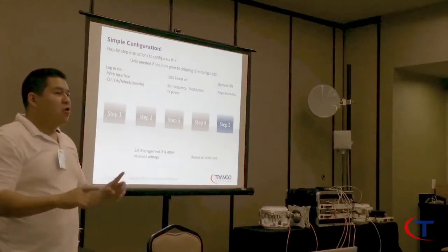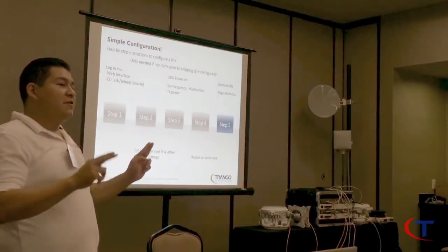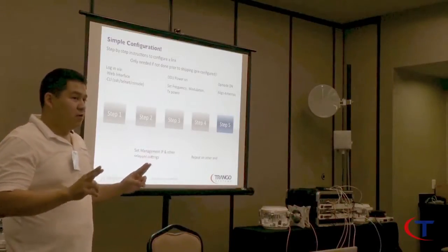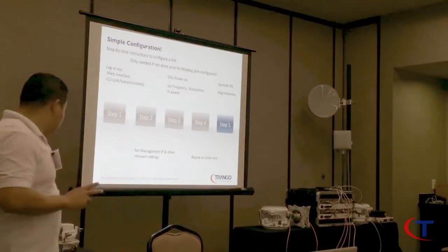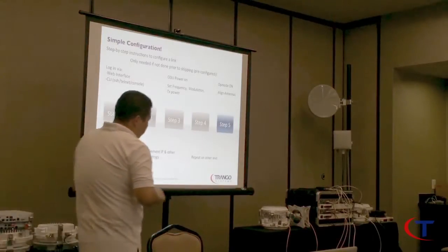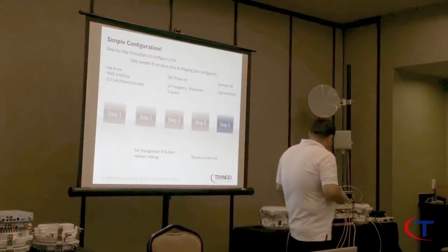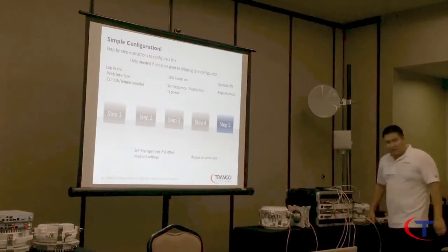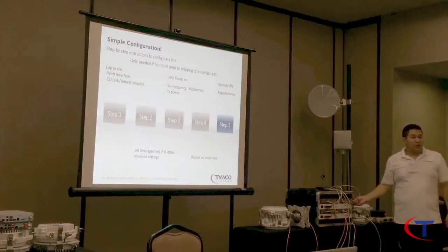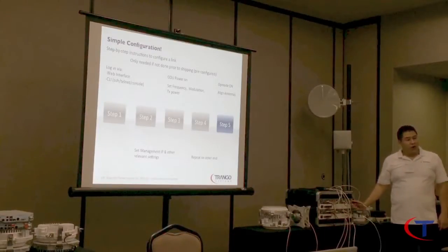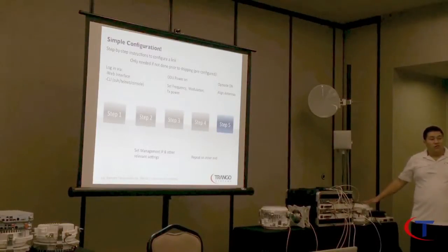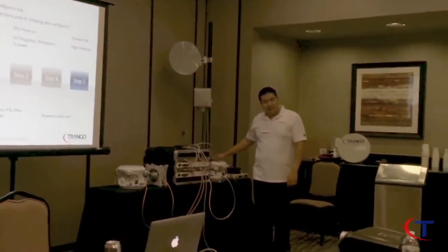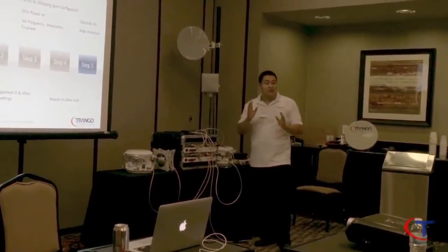There's 2 things here. ODU power on is different than op mode on, transmitter on. ODU power on gives power to the ODU unit. So, ODU power off means the IF cable, the LMR 400, is not going to carry any negative 48 volts to the tower. ODU power on means this is carrying the actual negative 48 volts. And you can read this. Transmitter on and off means this is not going to transmit. It's just going to be listening all the time.